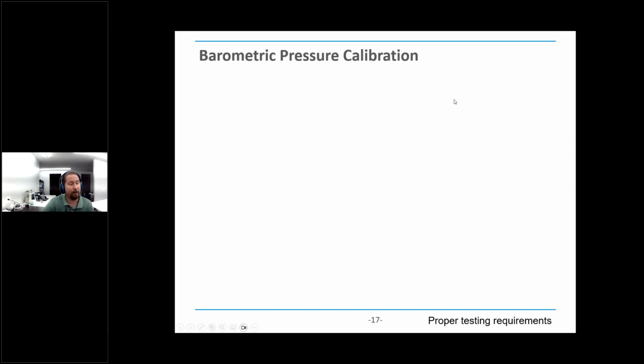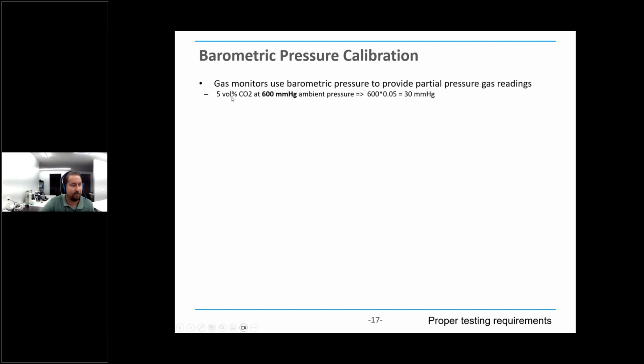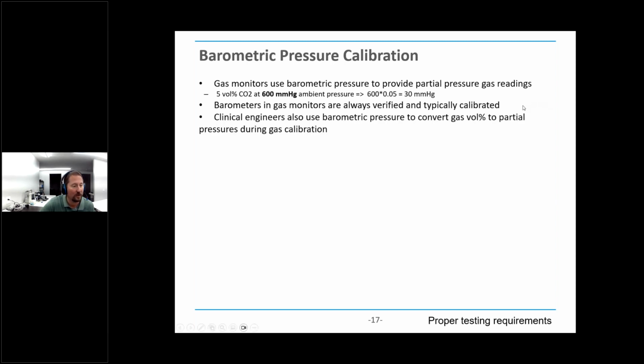We're going to talk briefly here about barometric pressure and its calibration. The devices use barometric pressure to get a partial pressure of the gas reading. So for example, if I've got 5% CO2 at 600 millimeters of mercury, that's my ambient pressure, that's a 30 millimeters of mercury partial pressure. Those are the measurements it uses to provide to the medical staff. Well, the problem is, barometers always want you to verify the barometer and the readings, and a lot of them can be calibrated. So that needs to be checked out. You also use it when you're spot checking or calibrating, because you often have to convert the calibration gas to a partial pressure. So you'll need access to a good barometric pressure.